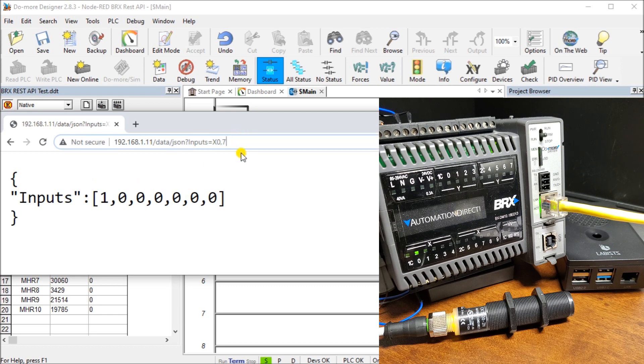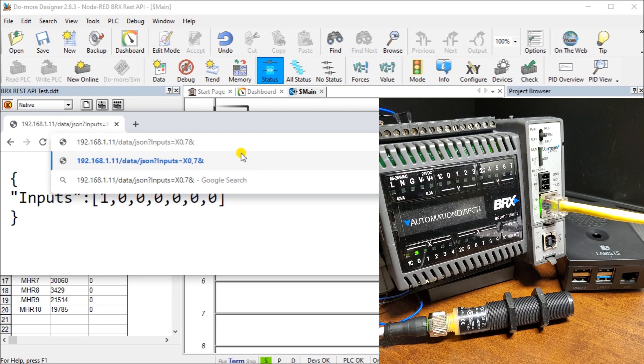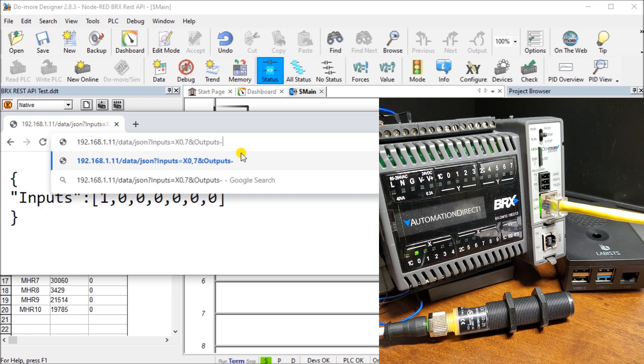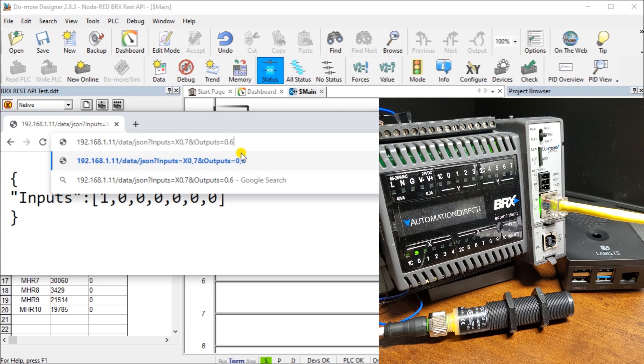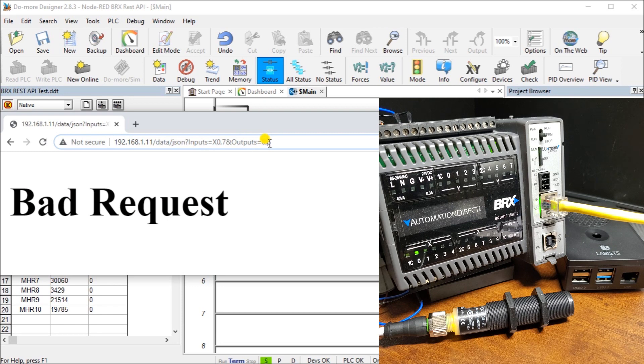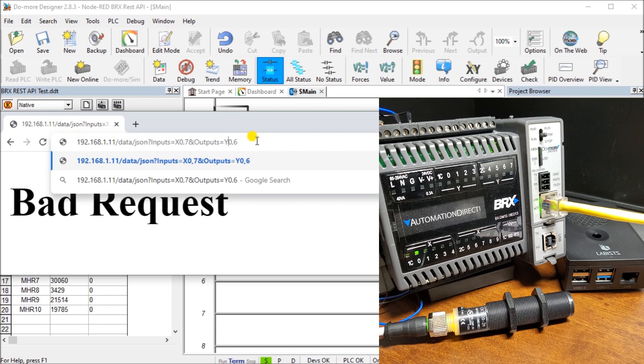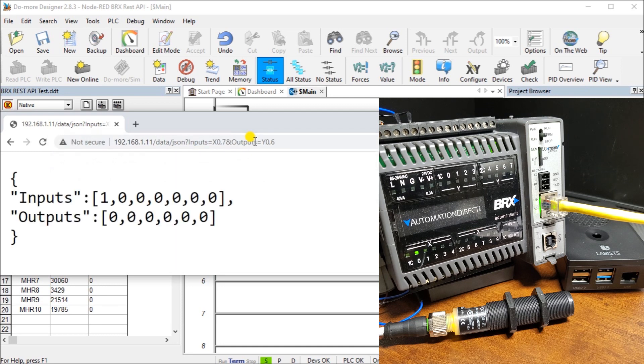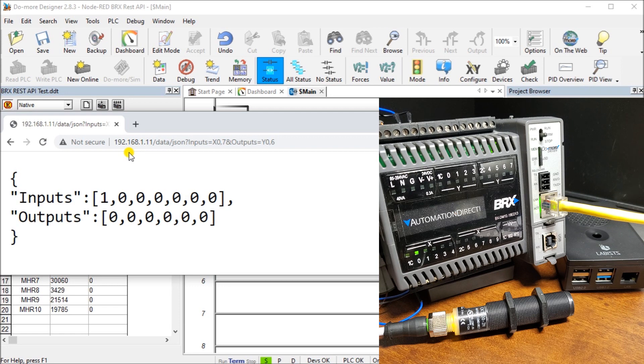Here you can see that I'm reading my inputs. If I need to read outputs at the same time, all I do is add the AND sign. I can say outputs equals from zero, and we'll read six of them. Hit enter. And now bad request, because I forgot to put a Y in here. Y zero, which is the actual address itself. Hit that. And now you see my inputs and outputs.